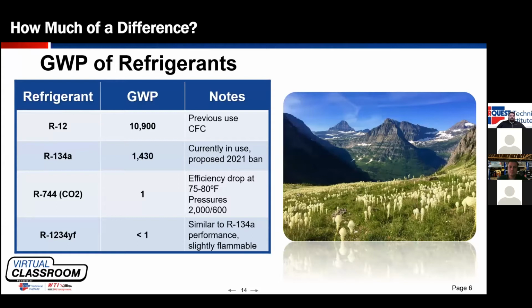Because of that, to use it in a car air conditioner, it has to be used in a secondary loop system. There is one vehicle manufacturer that is currently experimenting with it. There is nothing in production yet. CO2 was the direction GM initially thought they were going to go. They found that there is a big efficiency drop in warm weather compared to 134A when using CO2, and that the pressures are incredibly high. We're talking pressures 10 to 20 times the working pressures of 134A.